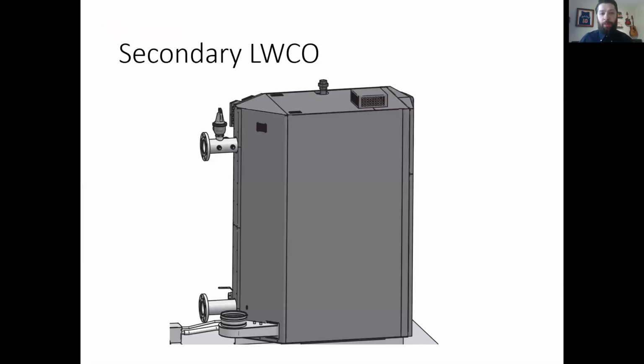So in New York City, they want a secondary low water cutoff on all these boiler installations. A lot of people always ask, where do I put that secondary cutoff? First of all, the initial one is standard equipment. We're going to ship out all of our boilers with one pre-installed. So the first one's inside the boiler. The second one, you're going to want to put right there when you can.